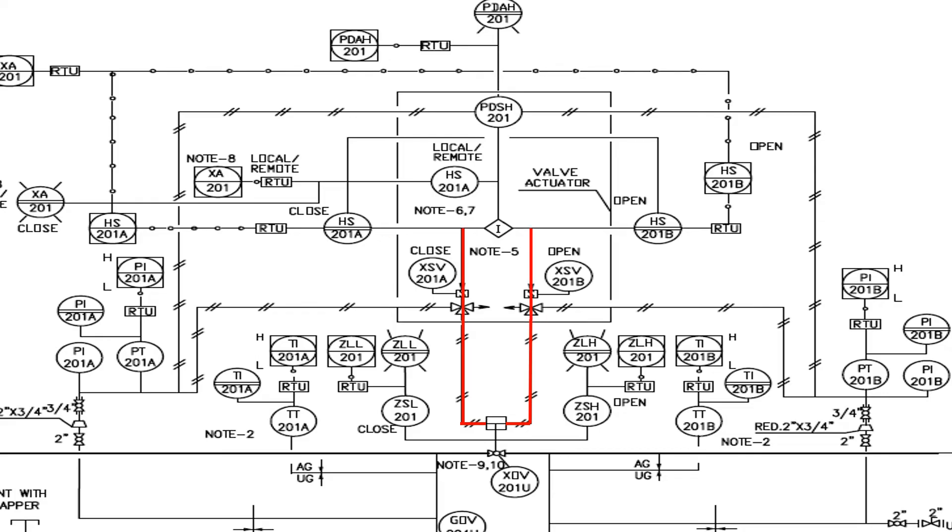Both the solenoid valves are connected to a differential pressure switch PDSH through an interlock logic, which determines when to open or close the XOV valve.